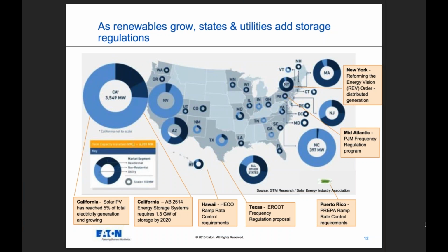The utilities have these large generators spinning, burning either oil, fuel, or nuclear. Since they don't have as many generators, when one suddenly drops out, the frequency slows down, so instead of receiving 60 cycles on your AC line, you might receive 59.8, 59.7, 59.6. It turns out operating those large, massive generators below about 59.6 shortens their life.